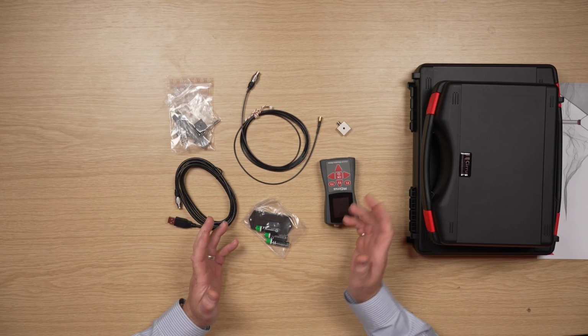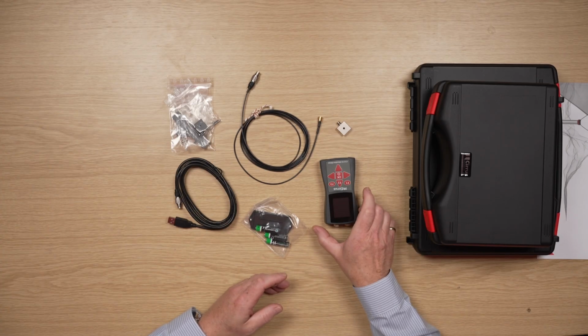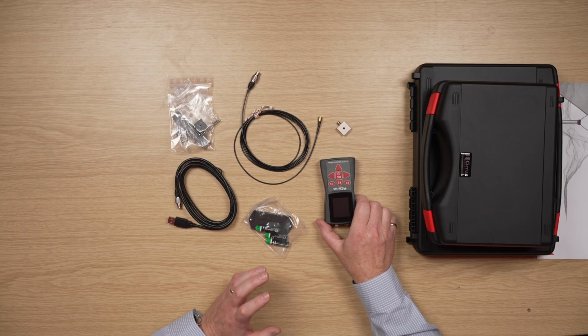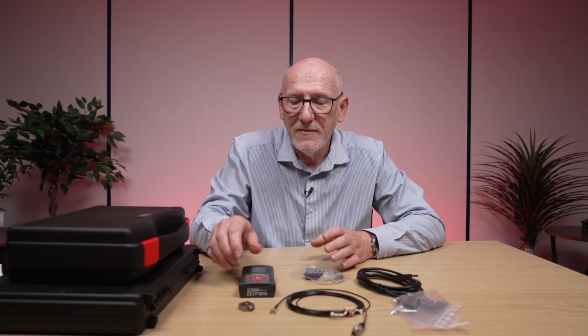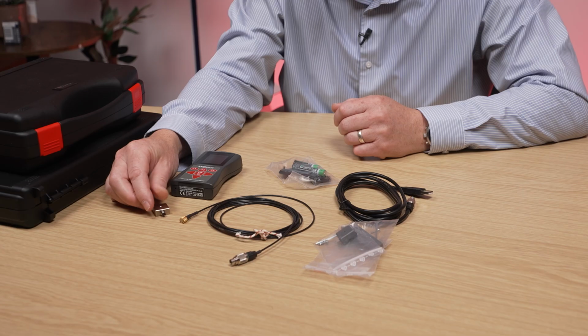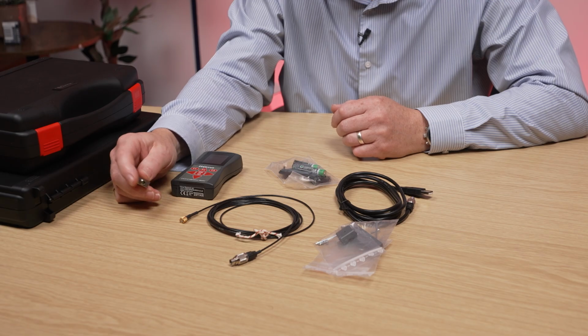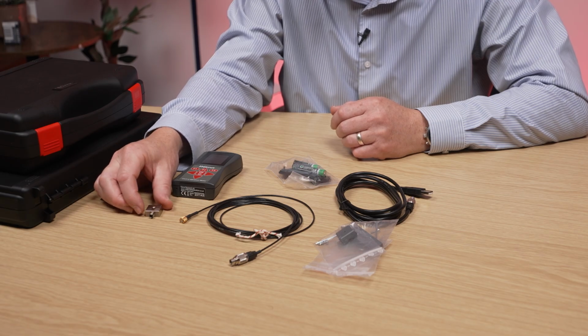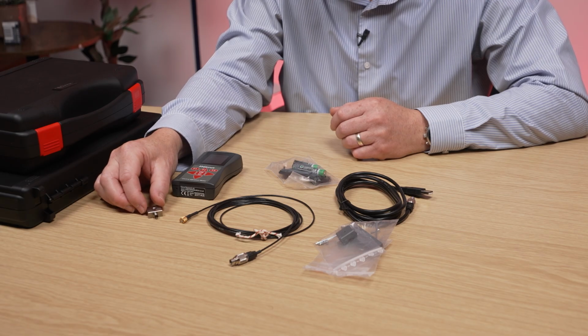So here's what was in the case. So what have we got? Well, we've got the actual meter itself that does all of the measuring. We've got this little piece here which is our transducer. In this case it's a triaxial accelerometer which measures the actual vibration.